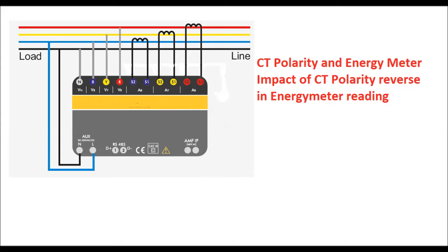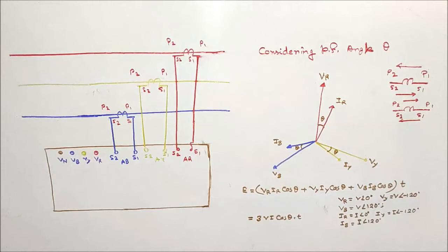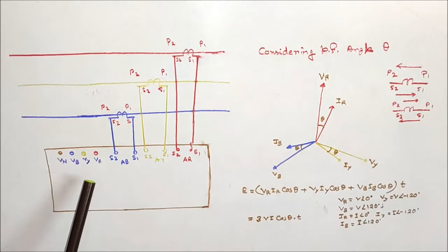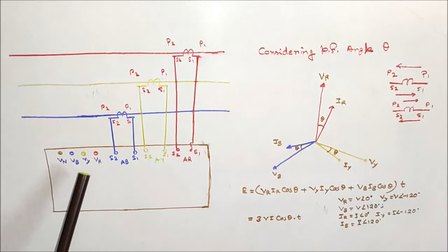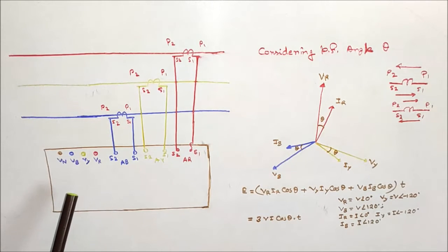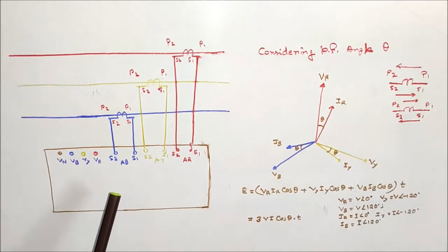In this diagram, a three-phase four-wire energy meter has been shown. The voltage input is red, yellow, blue, and neutral — that is why it is called a four-wire system. There also exists a three-phase three-wire system, where only red, yellow, and blue phase voltage input is taken, and only red and blue phase CT secondary input is taken to the energy meter.